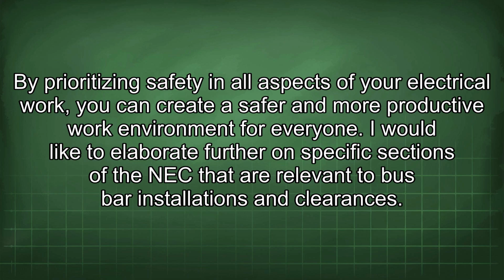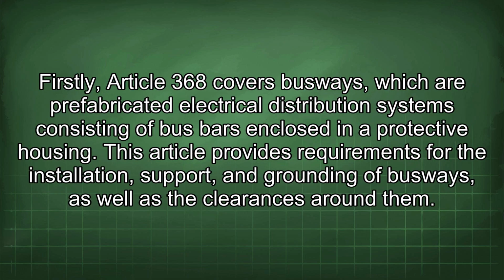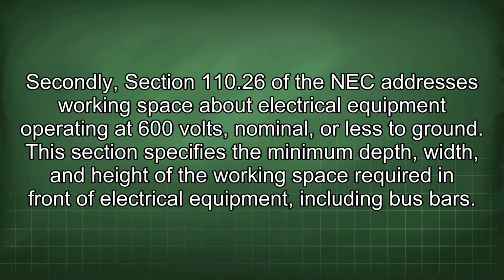for everyone. I would like to elaborate further on specific sections of the NEC that are relevant to bus bar installations and clearances. Firstly, Article 368 covers busways, which are prefabricated electrical distribution systems consisting of bus bars enclosed in a protective housing. This article provides requirements for the installation, support, and grounding of busways, as well as the clearances around them. Secondly, Section 110.26 of the NEC addresses working space about electrical equipment operating at 600 volts, nominal, or less to ground.